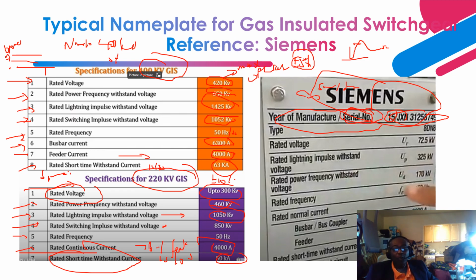Next is the rated voltage. The nominal voltage is 69 kV, and the maximum is 72.5 kV. So as you can see, it's about plus 5% above the nominal. Next is your rated lightning impulse withstand voltage, 325 kV. The power frequency overvoltage, 170. The rated frequency, 50 or 60 Hz.